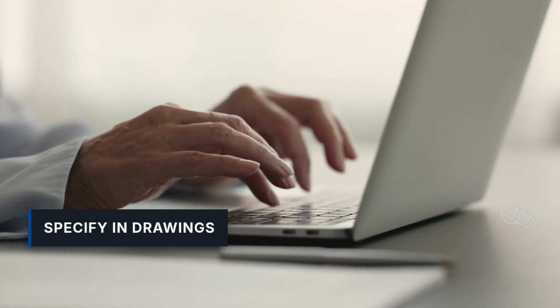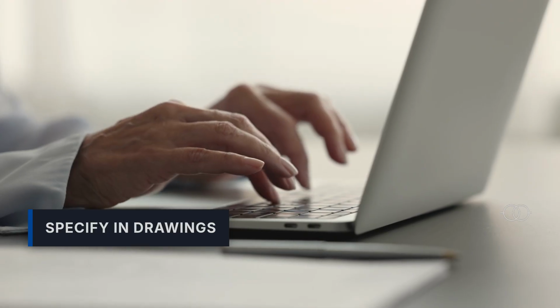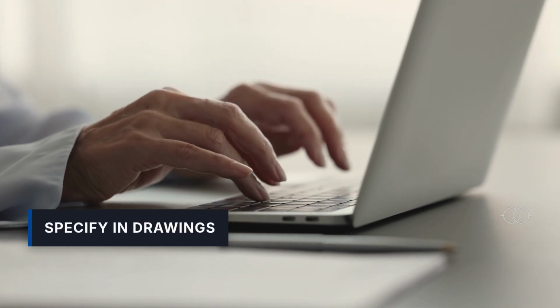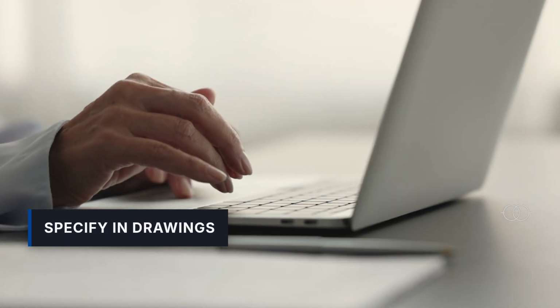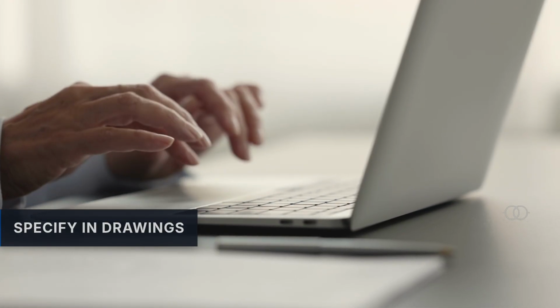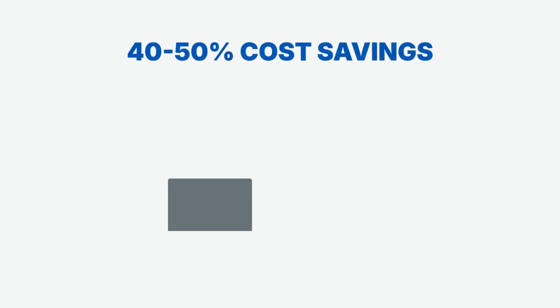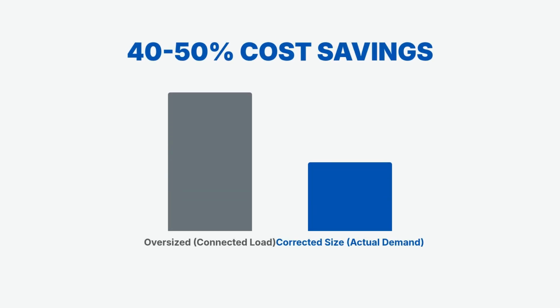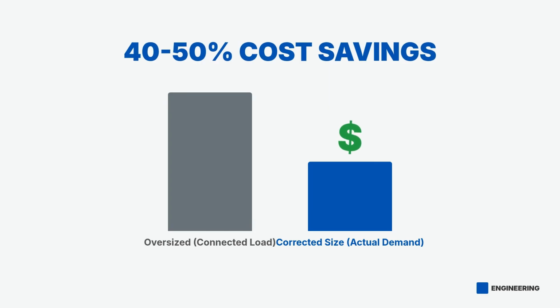Use these values to specify transformers in your electrical drawings and equipment schedules, ensuring adequate capacity without excessive capital expenditure. Here's a critical insight. Never confuse connected load with actual demand. Using connected load directly leads to transformers oversized by 40 to 50%, wasting thousands in unnecessary costs.